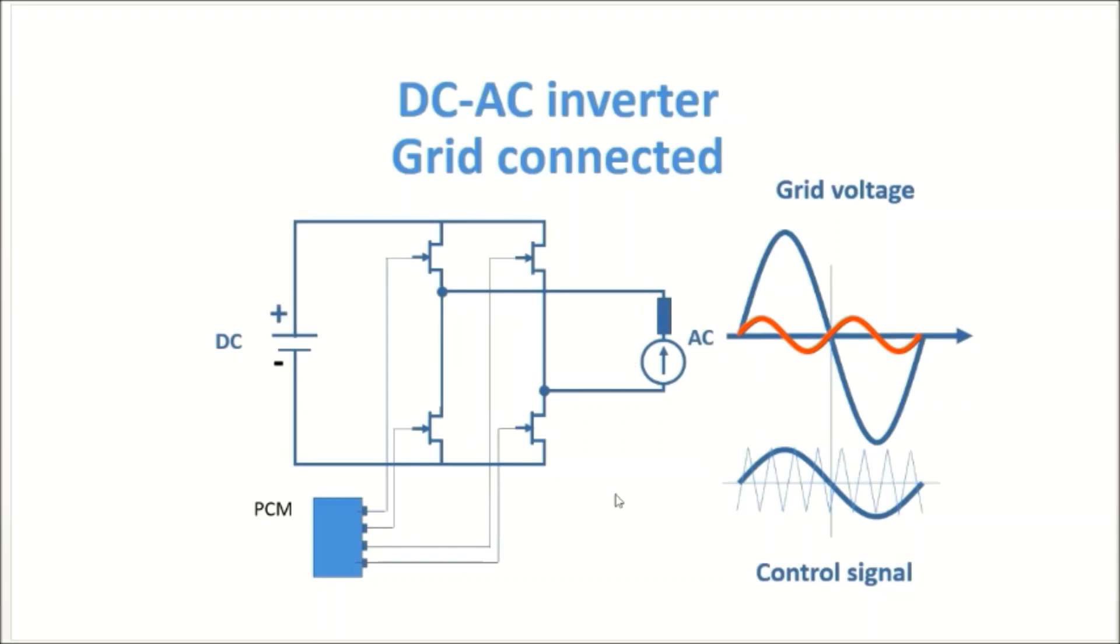In order to do so, we will start to give the control signal a certain phase shift compared to the grid voltage signal, meaning we start to give it the leading edge. Then you can see how we give it a leading edge, so we move it in this direction. And as a result, we see that the power from the battery starts to be pushed into the grid.